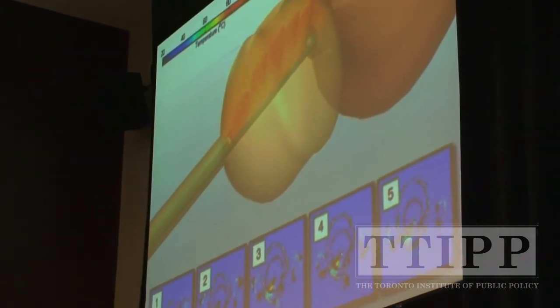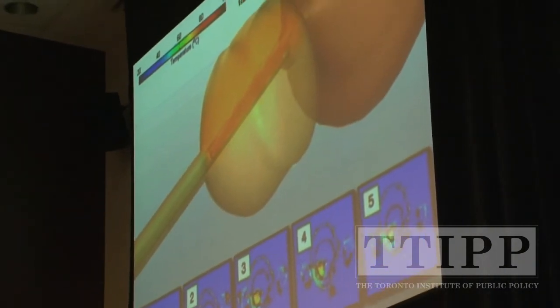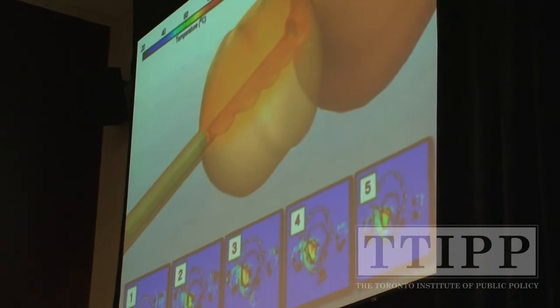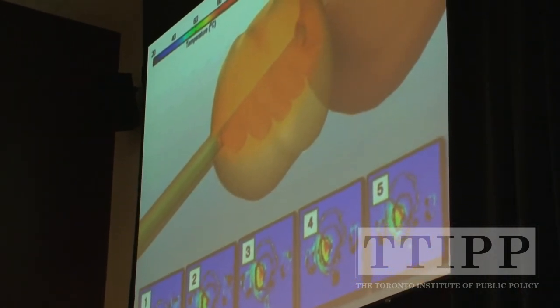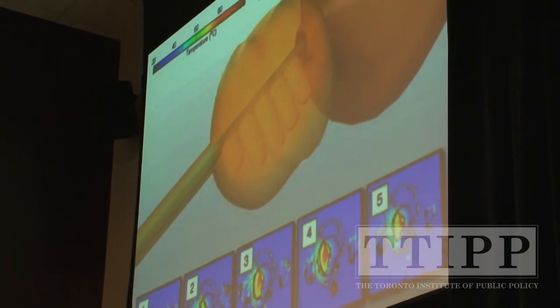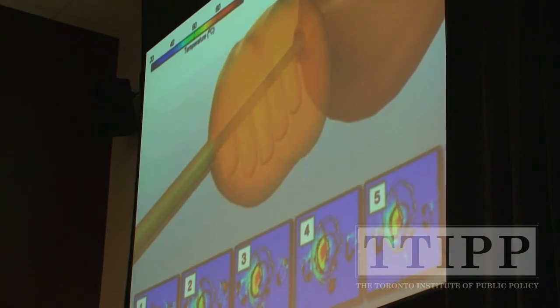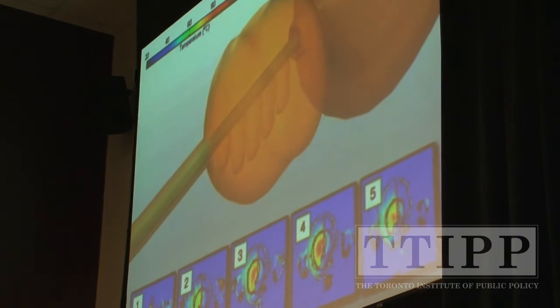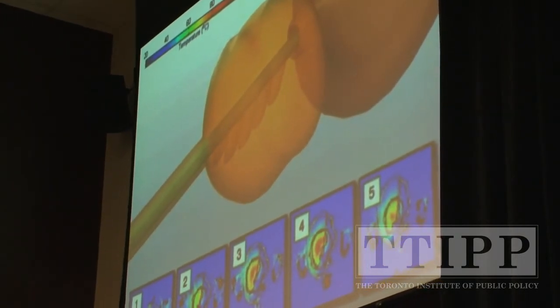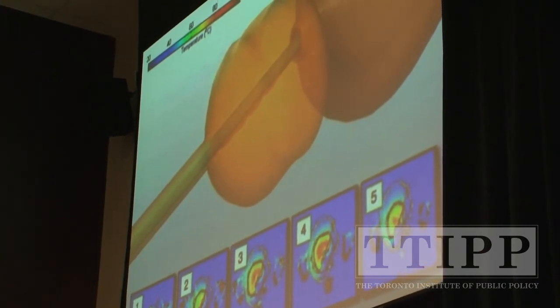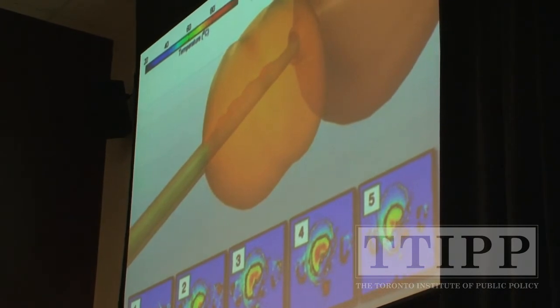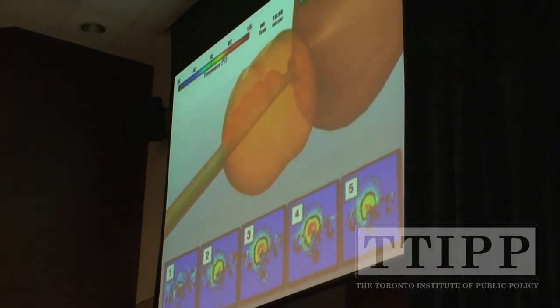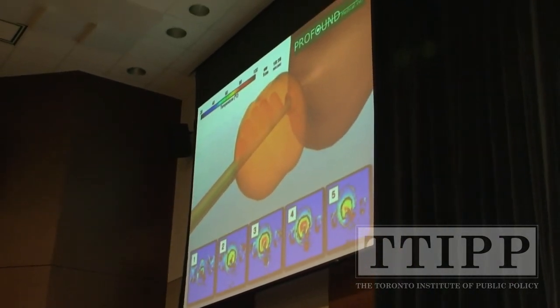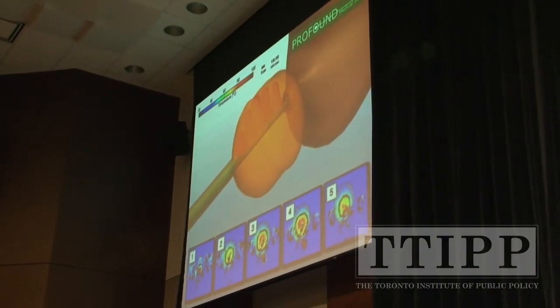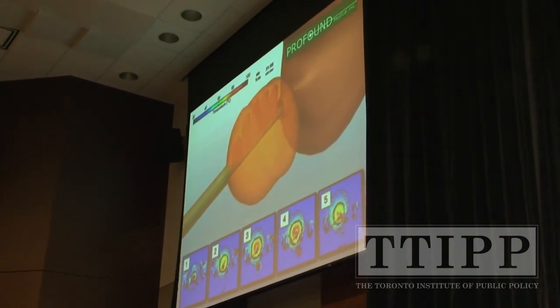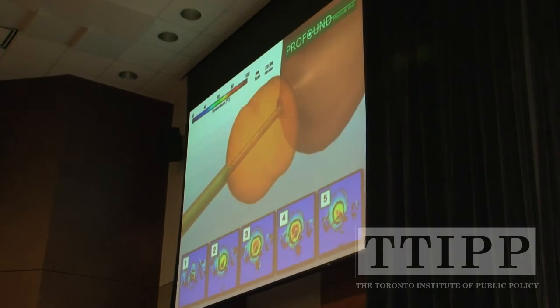The ultrasound transducers generate a series of parallel collimated energy beams that deliver thermal denaturization at a minimum 56 degrees Celsius under real-time MRI guidance and feedback to the prescription boundary in a single radial 360-degree sweep. The treatment time is very fast, approximately 20 minutes. While this exemplifies the potential to treat a very large volume of prostate, the system has great potential for focal treatment, delivering energy to a specific subsector or segment of the organ, using as few or as many transducers as required. As can be seen, there is a high degree of agreement between target boundary and actual treatment boundary, typically representing plus or minus 1 millimeter, plus or minus 1 degree Celsius.